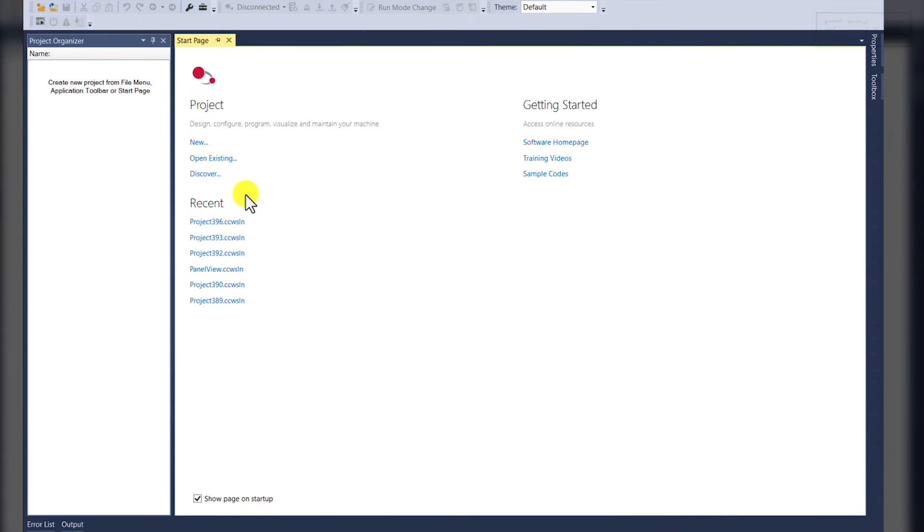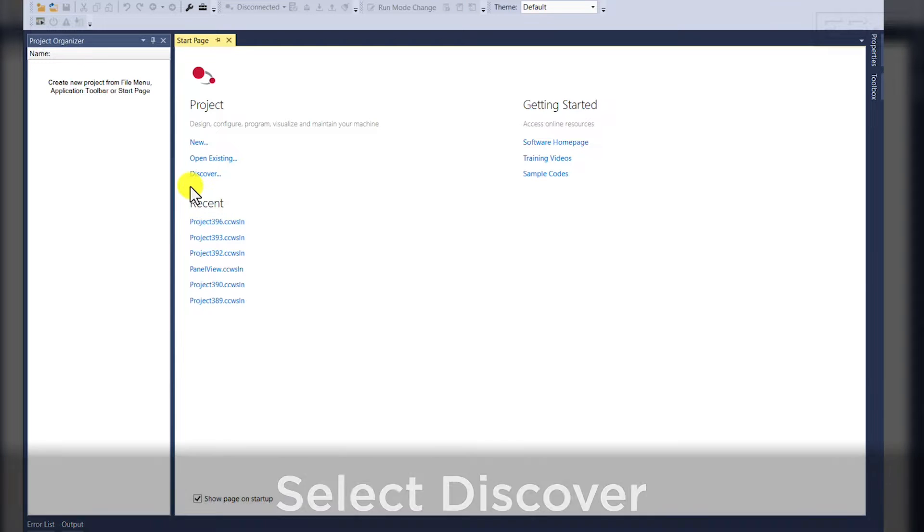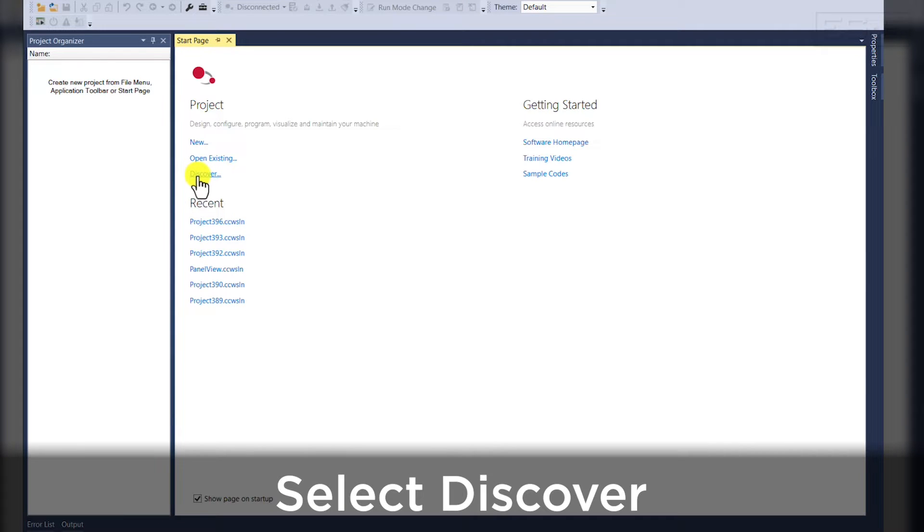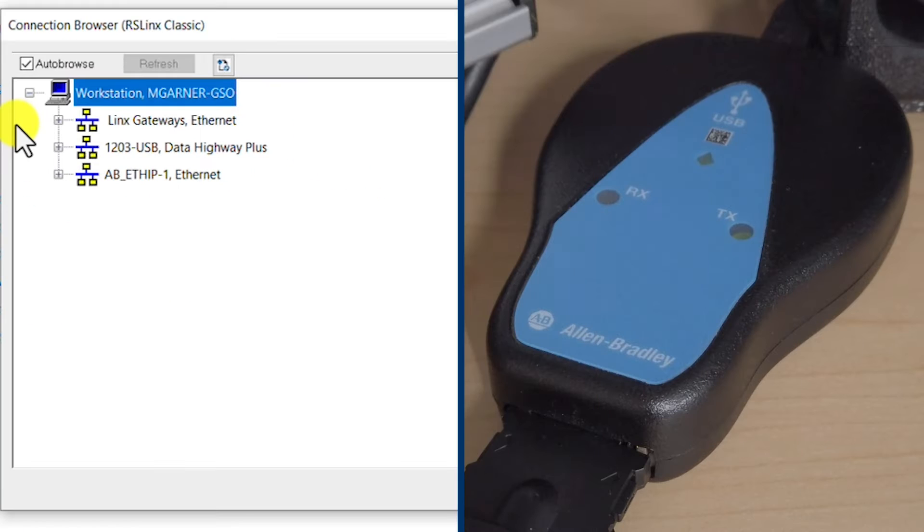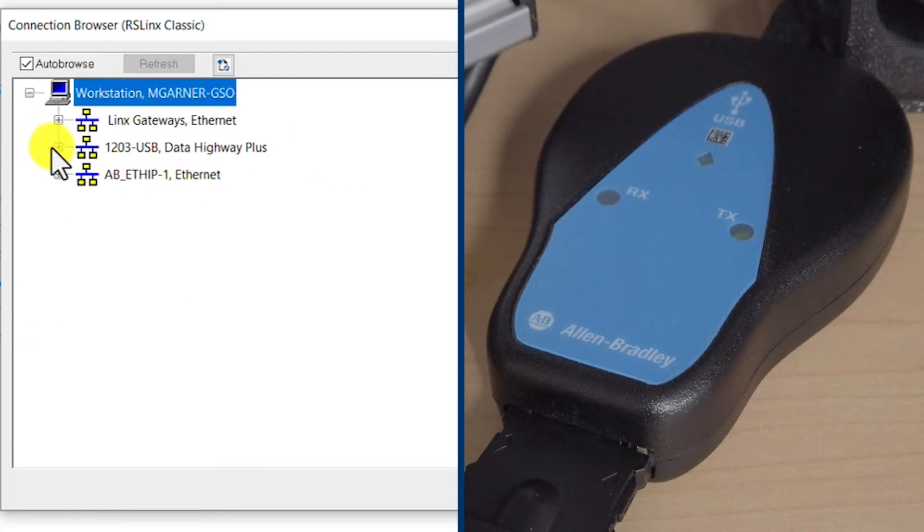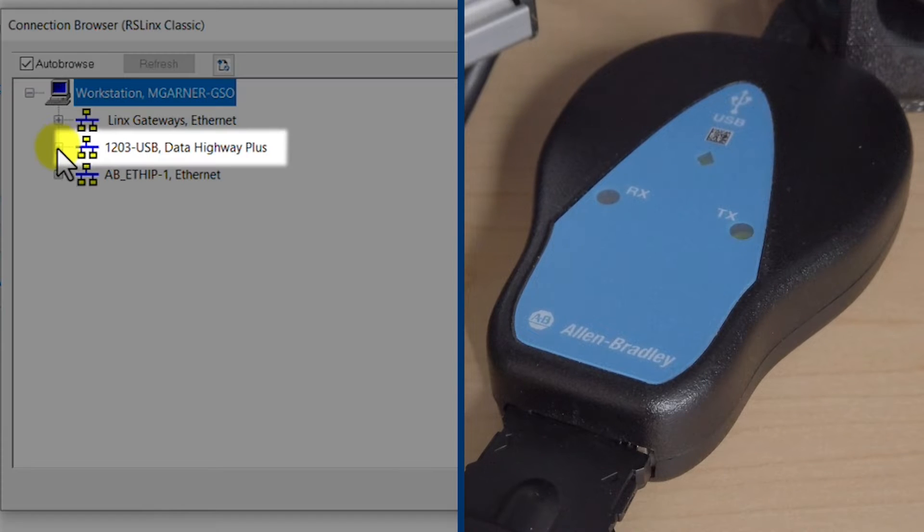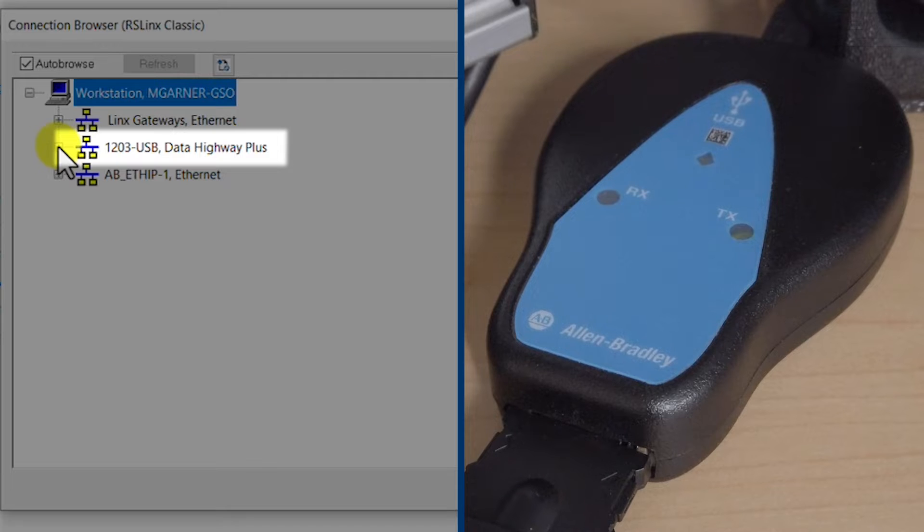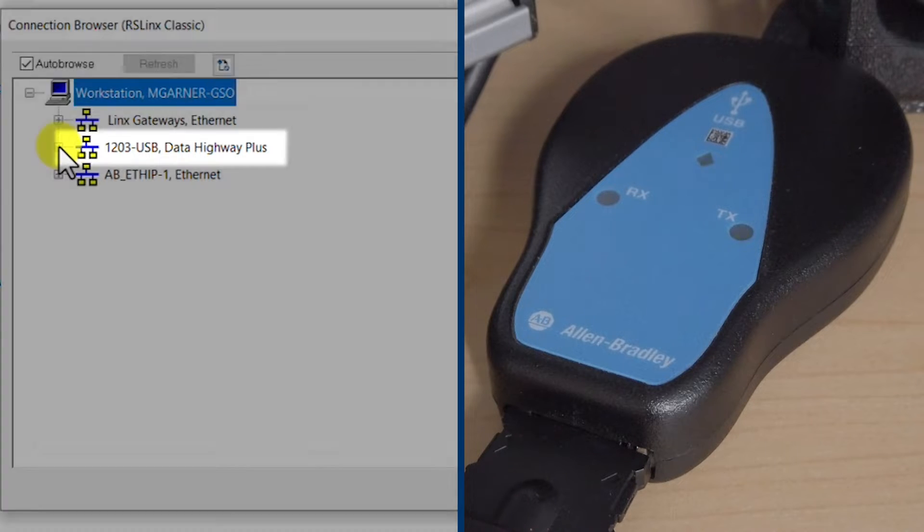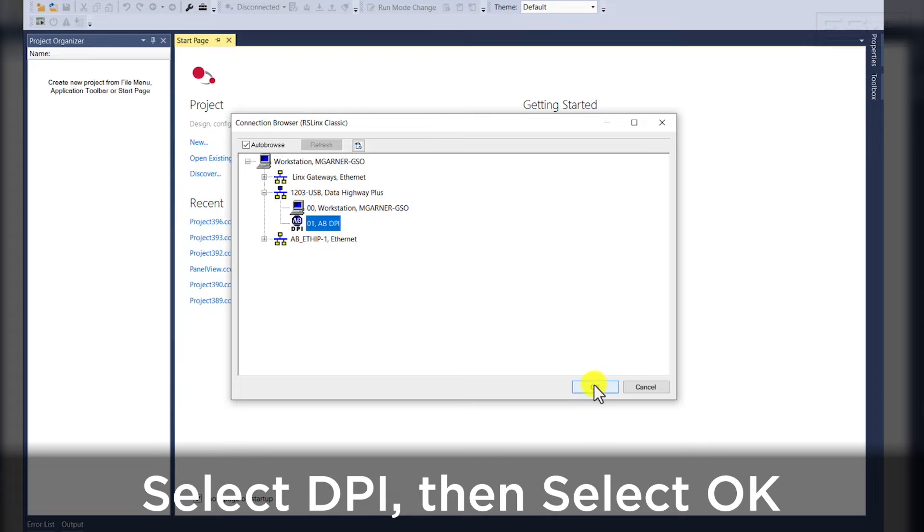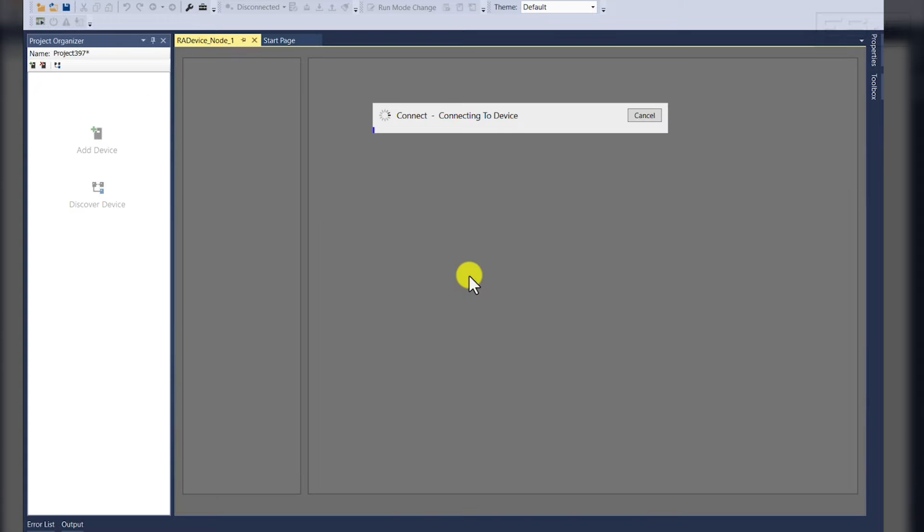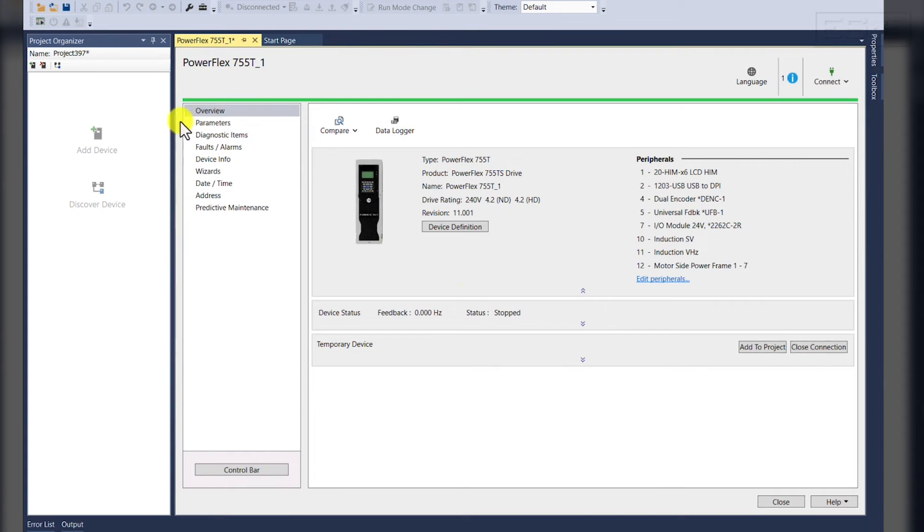First step in connecting to our PowerFlex 755 TS drive on Connected Components Workbench, we're going to click Discover. This is going to bring up your RSLinx, and we're going to want to use the 1203-USB Data Highway Plus driver that we have pre-configured. Once we point to the DPI port, we'll select OK, and you'll see that we are connecting to the device.